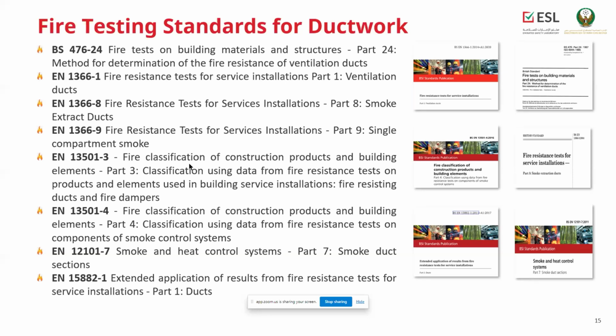For EN, part 1 targets only ventilation, and it includes ventilation and kitchen extract together. For smoke control, it comes under either part 8 or part 9. Part 8 is for multi-compartment, and part 9 is for single compartment. We have the classification of the results that come from these three EN standards. It needs a classification to standardize the rating that comes from the test result. That's why for the EN approach, there is a classification standard to standardize the rating. So we have EN 13501 part 3, which is for ventilation ducts, coming from part 1. And we also have EN 13501 part 4, which is the classification for smoke control ducts.